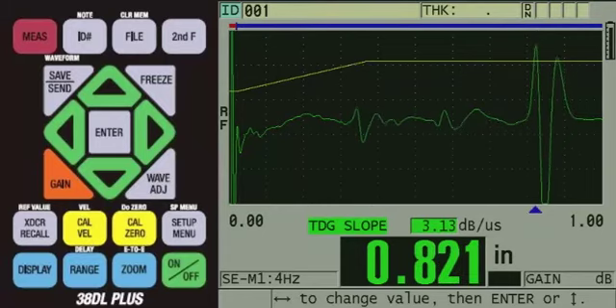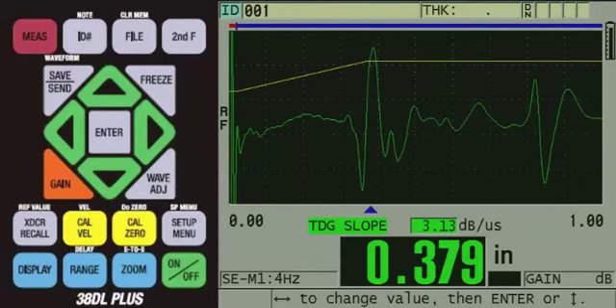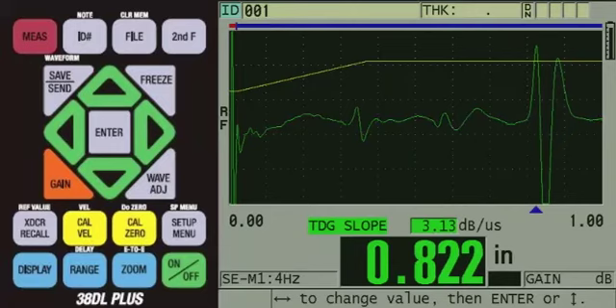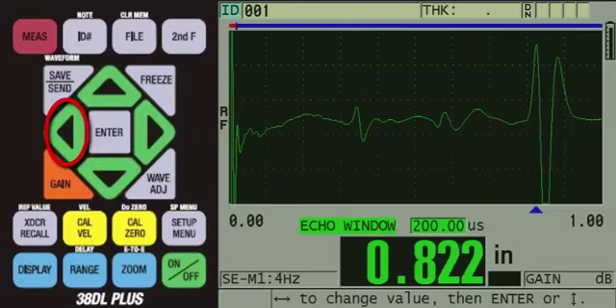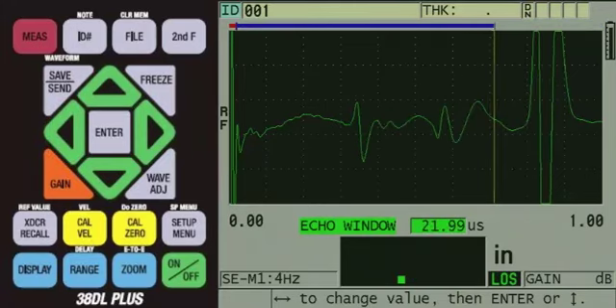Also, if the customer is only interested in measuring the distance to the steel cords and does not want to measure total thickness, they could decrease the echo window to prevent the instrument from detecting the total thickness echo. To do this, press the down arrow to echo window, then press the left arrow to decrease the echo window until it is set right before the occurrence of the total thickness echo. This adjustment takes some time, since the default echo window for the M1036 transducer is set large. This is because the M1036 is a 2.25 MHz direct contact transducer, which gives it great penetration capabilities. Once the echo window is reduced so that it does not include the total thickness backwall echo, when we scan the part, we will only get a reading from the steel cords.